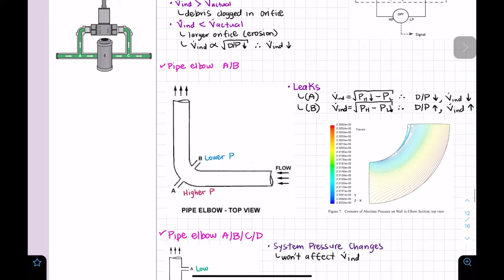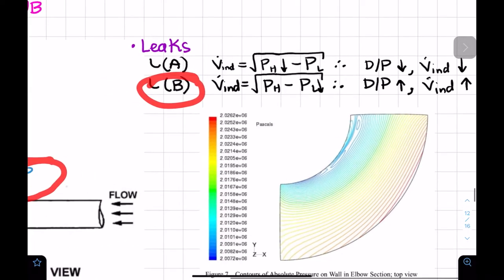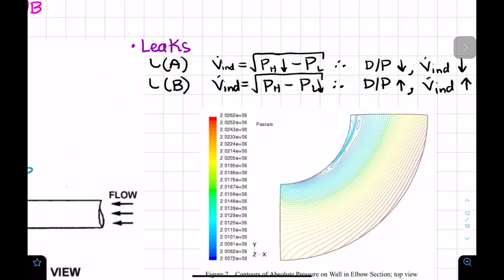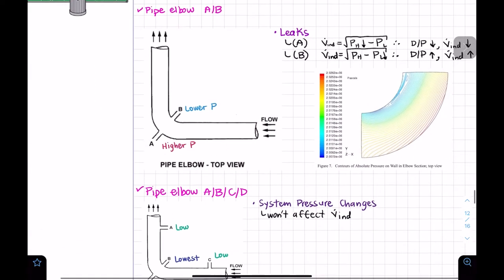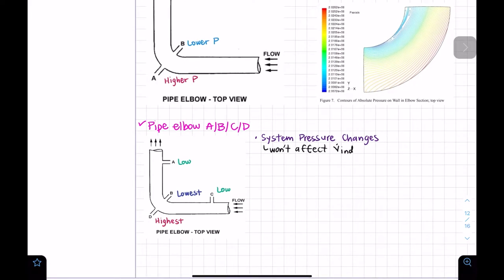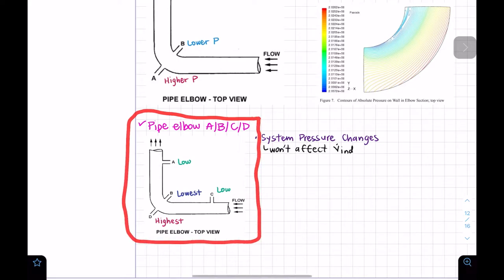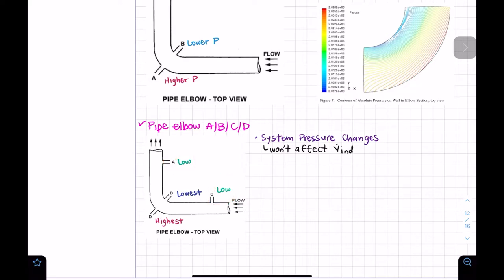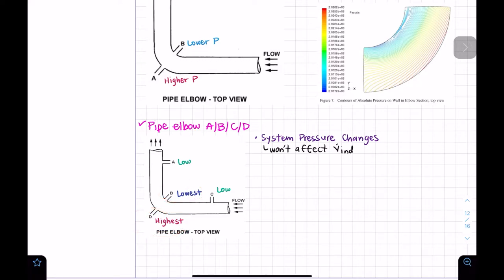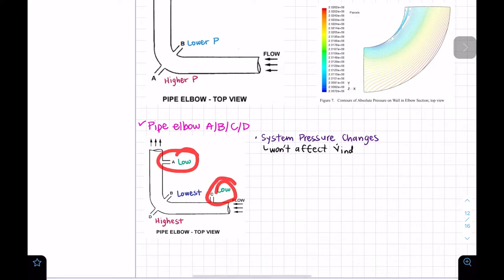Conversely, if there's a leakage on the lower side, we're lowering the low-pressure side further, which increases the differential pressure and therefore increases the indicated flow. That's all we need to know here. For the four-orifice elbow configuration, we have the highest pressure on the outer wall, the lowest pressure on the inner wall, and two additional taps that also read low pressure.